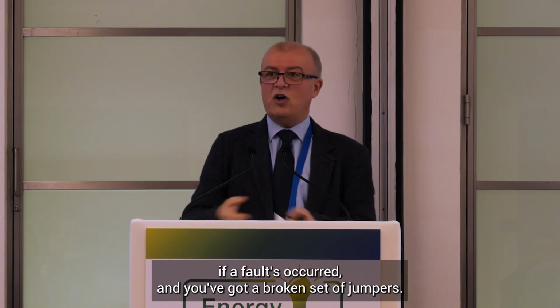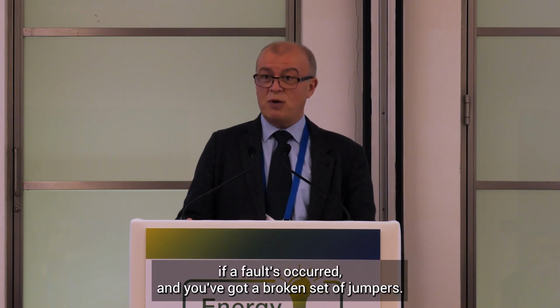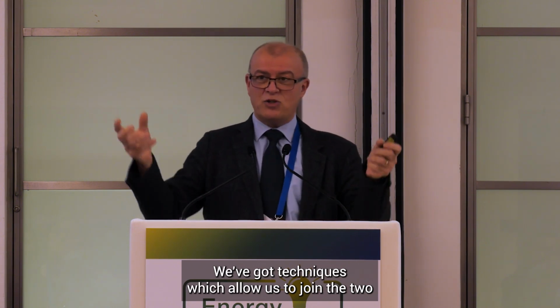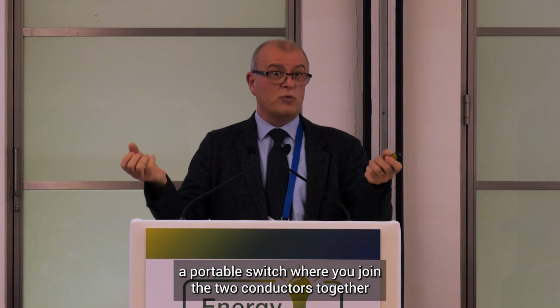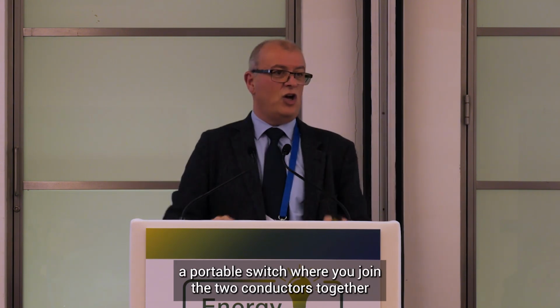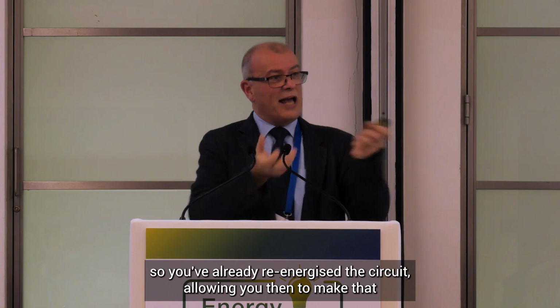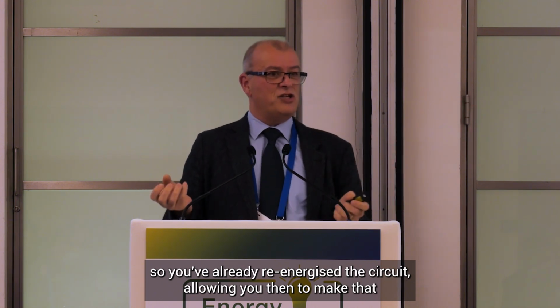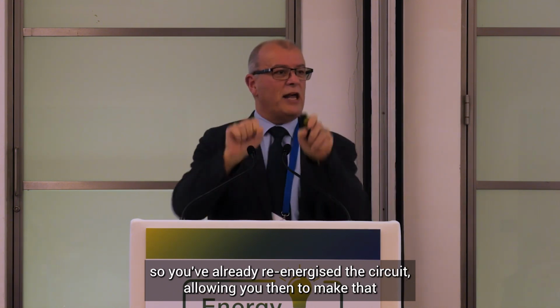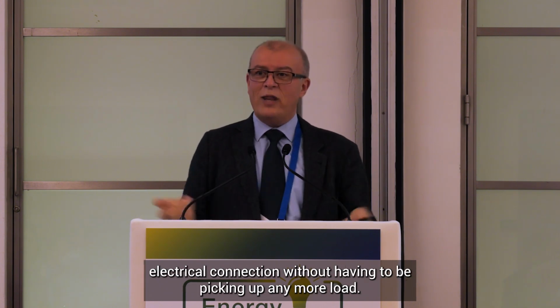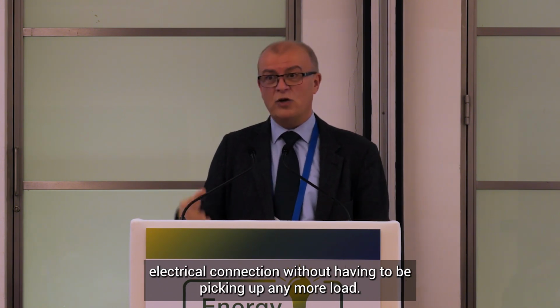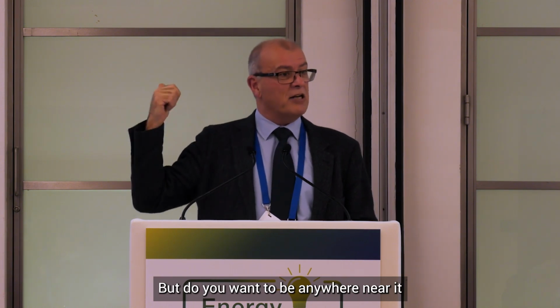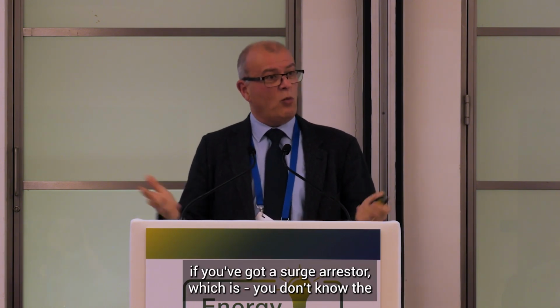We reconnect the network. No, if a fault's occurred and you've got a broken set of jumpers, we've got techniques which allow us to join the two, a portable switch where you join the two conductors together. So you've already re-energized the circuit, allowing you then to make that electrical connection without having to be picking up any more load.